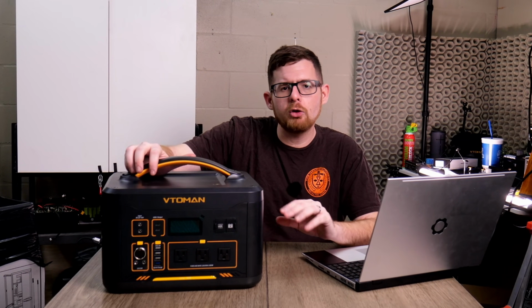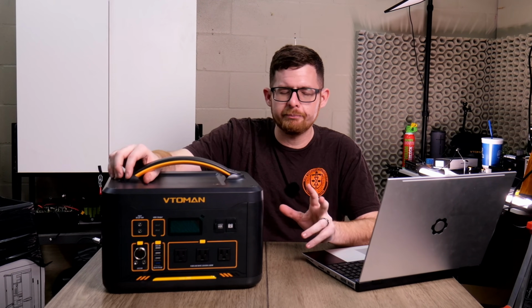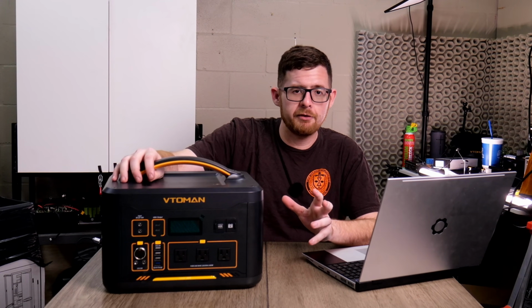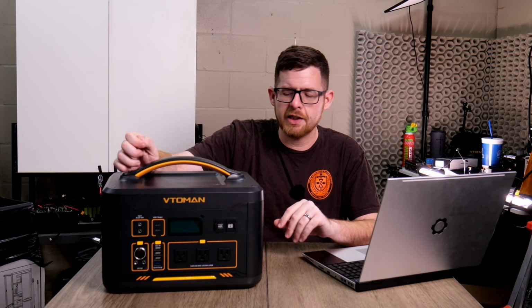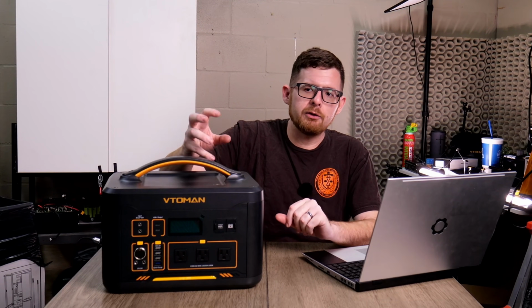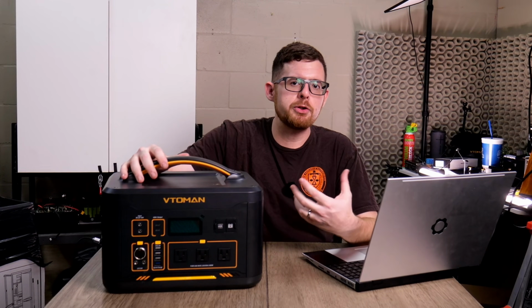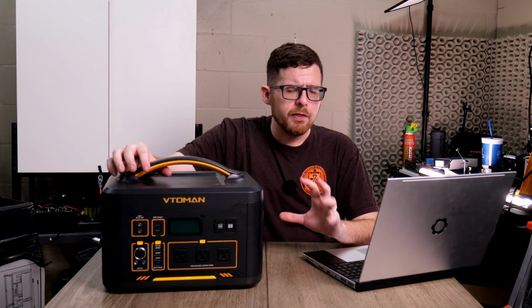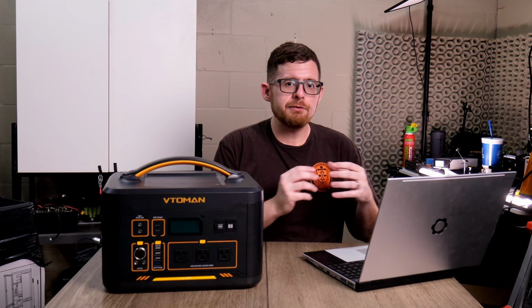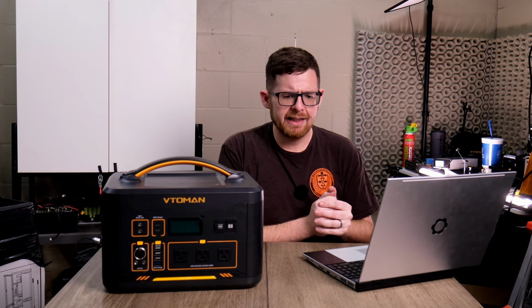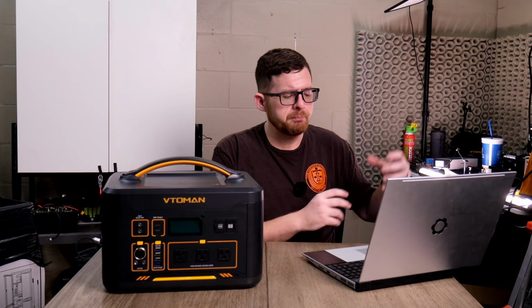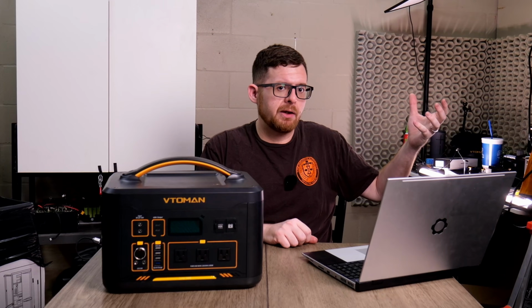Some of the earlier homes may not have that ground wire in there. You probably already know about it because it's probably caused you some trouble in the past, and we're not going to touch on those. Normally though, your ground wire ties back into the neutral line on your AC panel. The reason why that's done is because if you do have a short somewhere, like say a lamp on the outside of your home, and you just have a ground there...